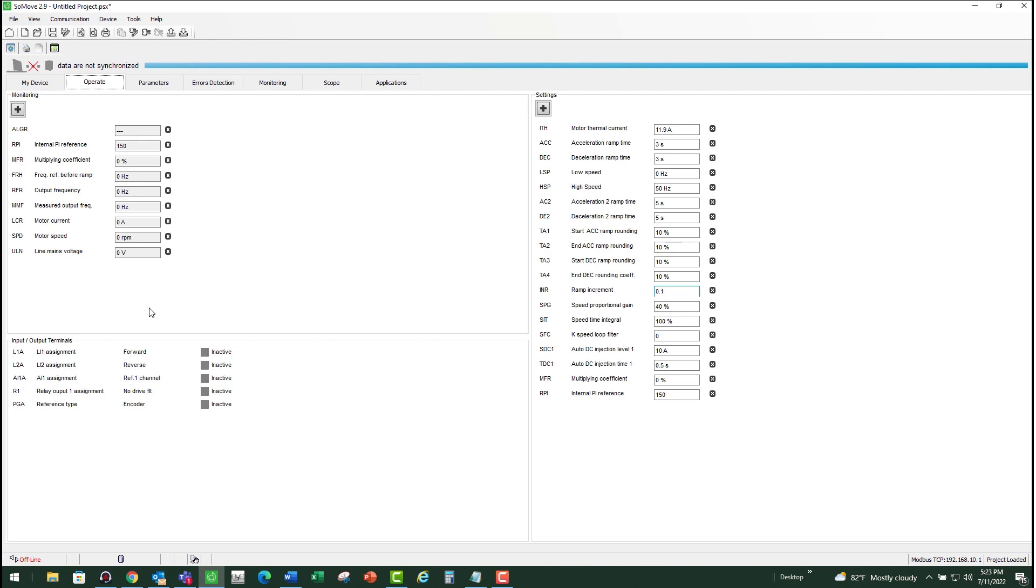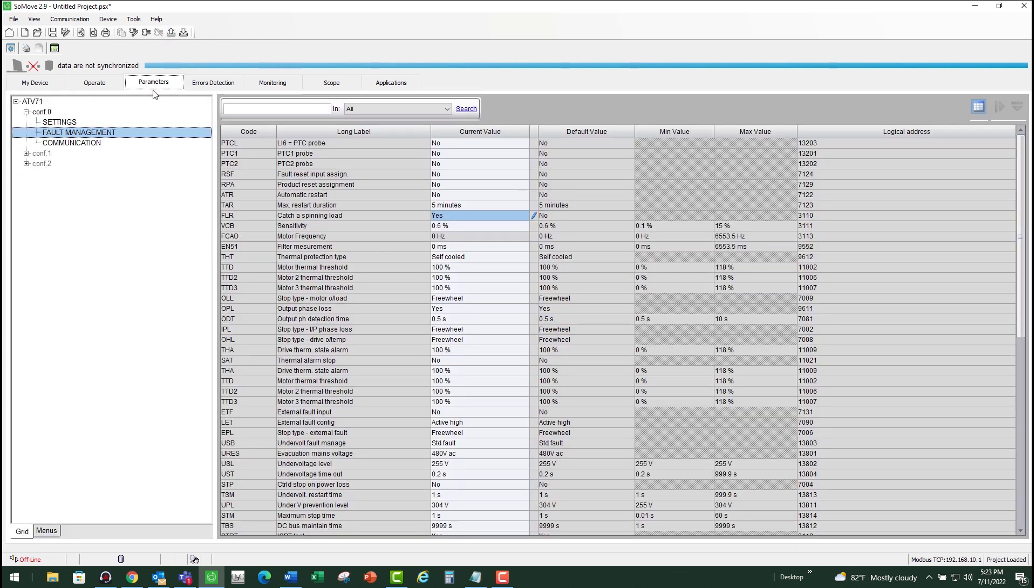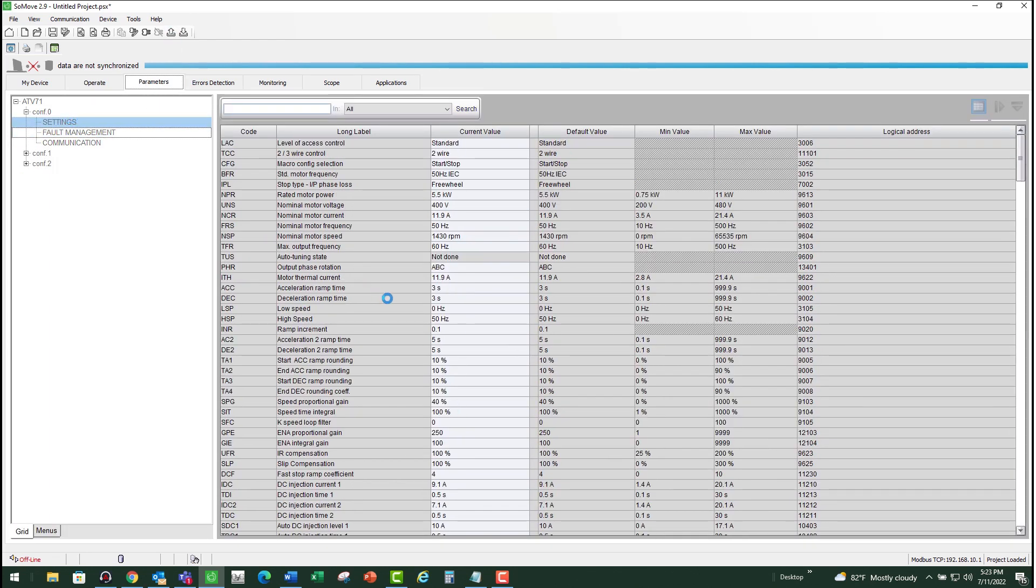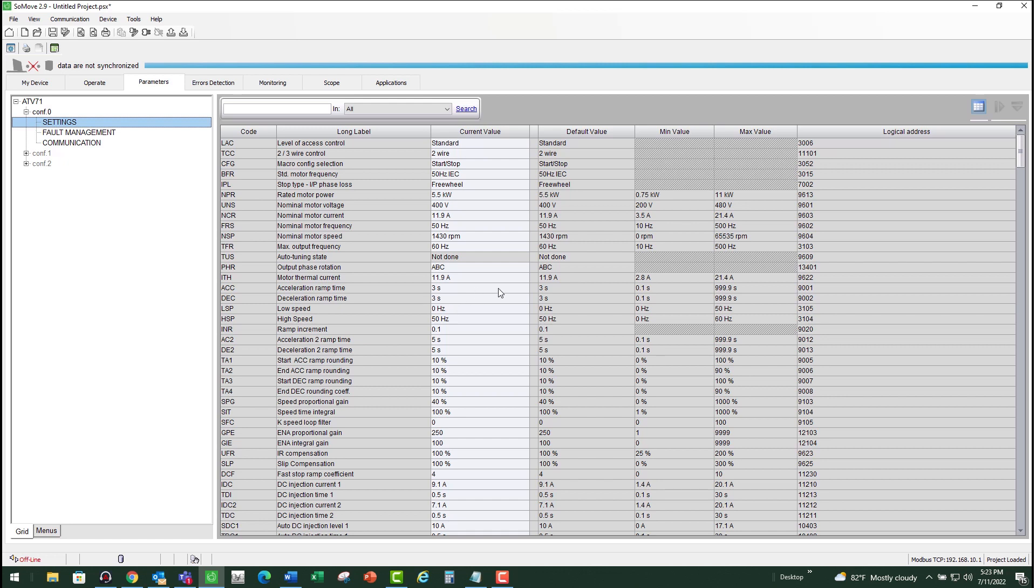The third scenario will be if the drive trips while decelerating. If that happens, then you need to increase the deceleration time. Again, it can be found under parameters, under settings, and your acceleration and deceleration times are listed right here. So you can try increasing the deceleration time to see if that helps avoid the trip.